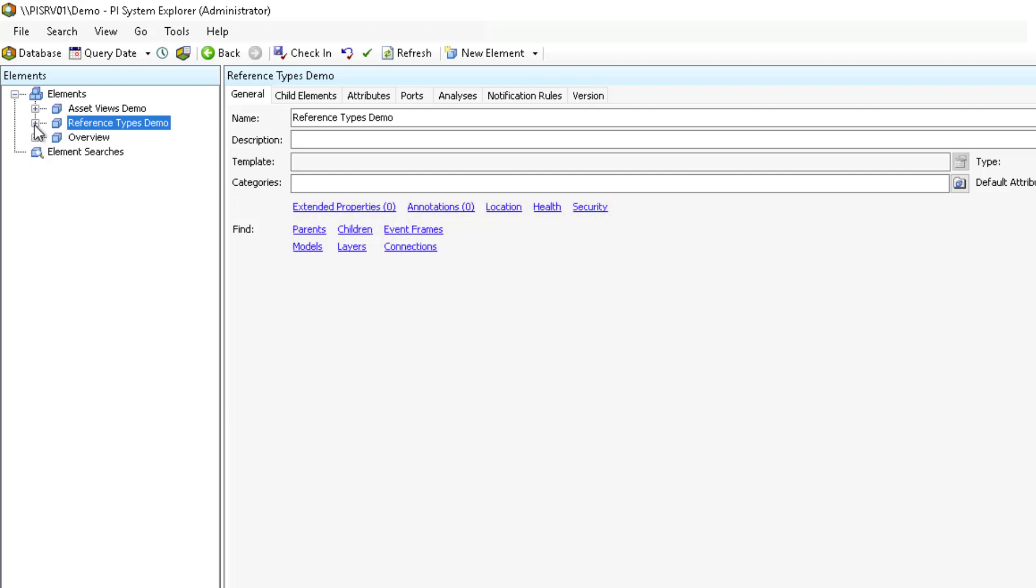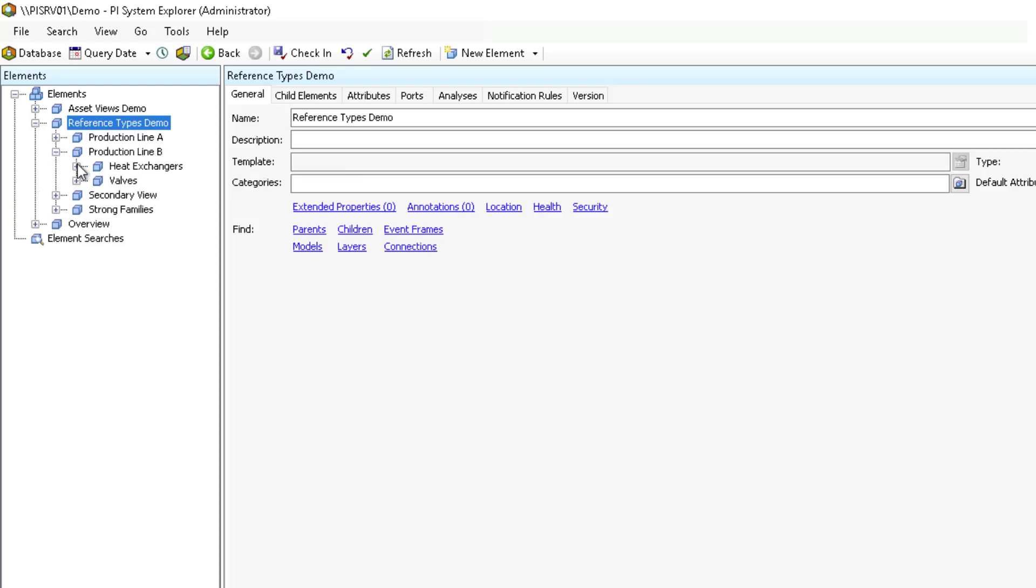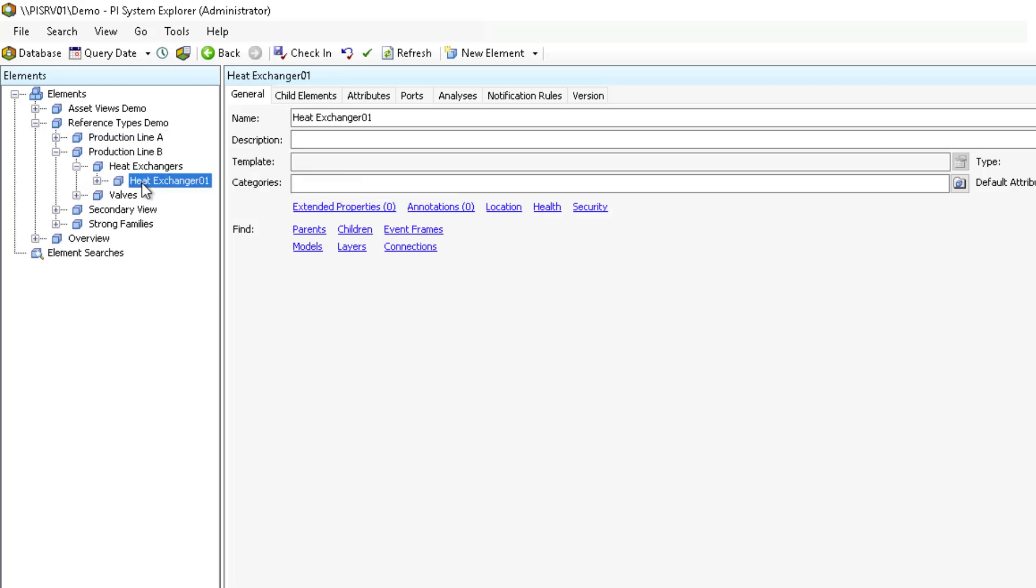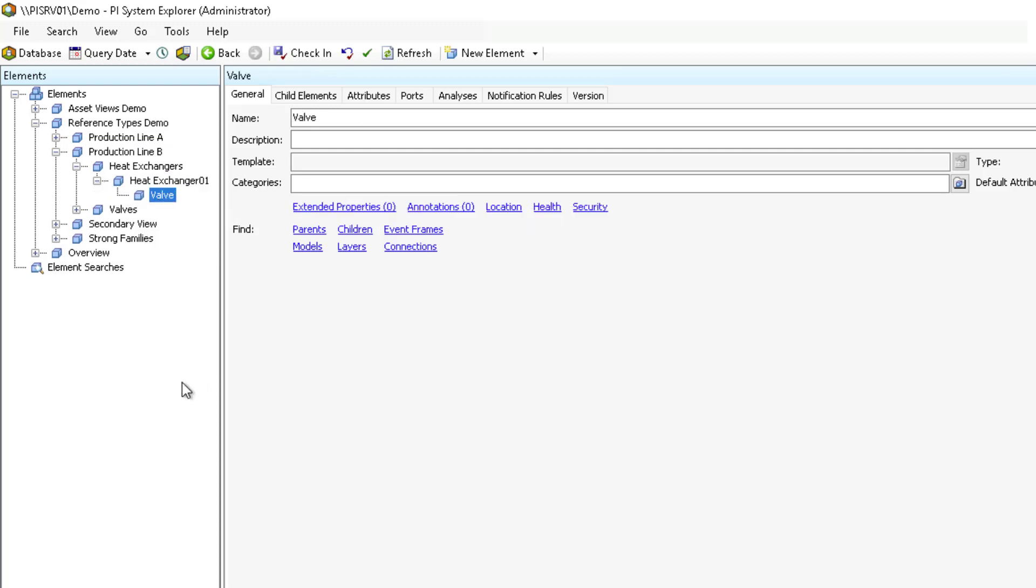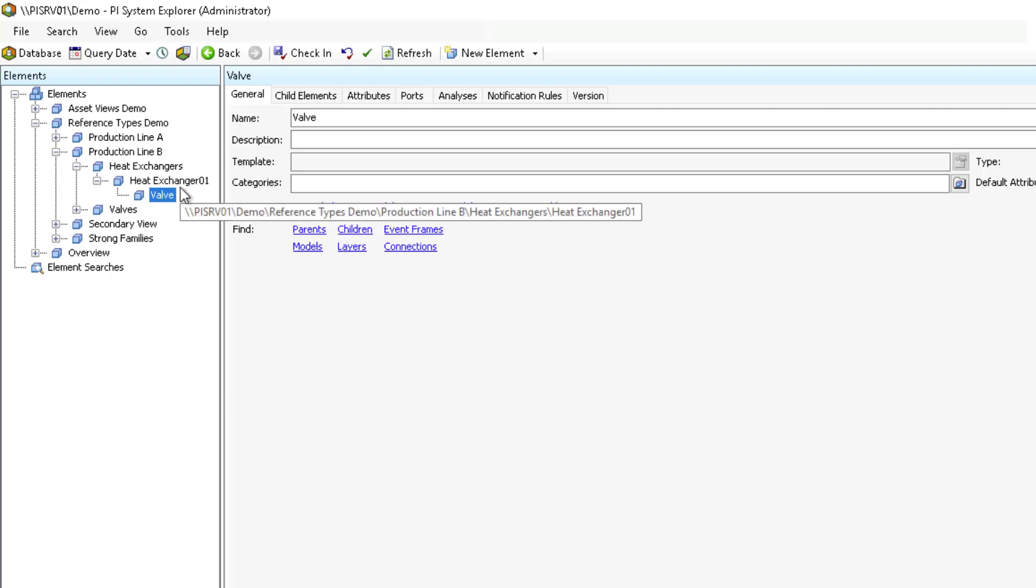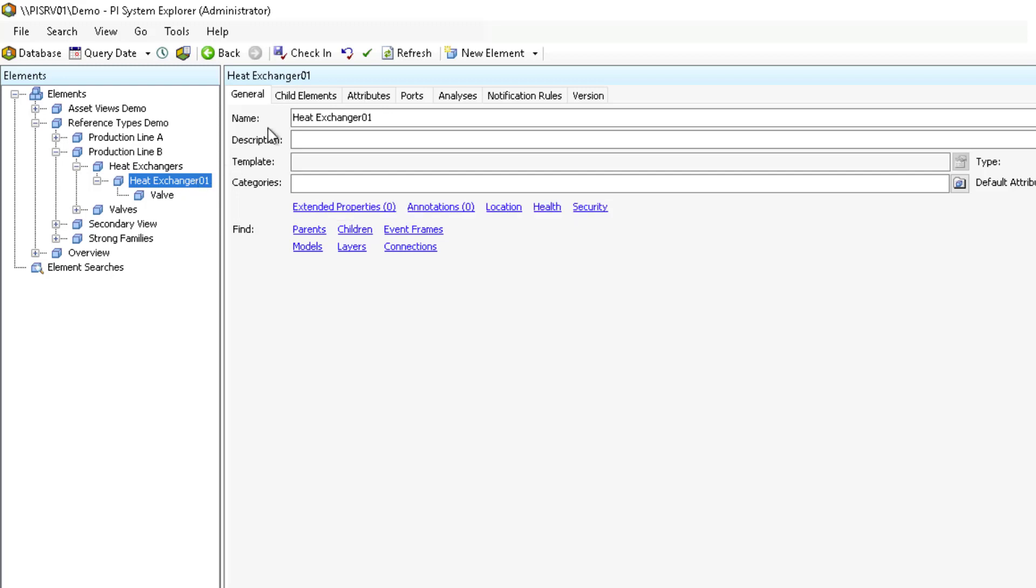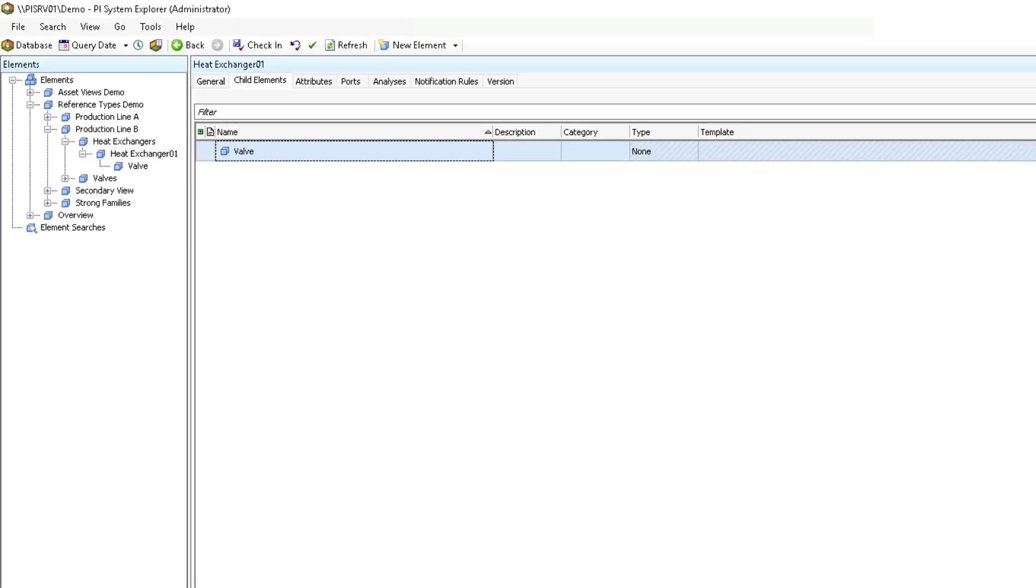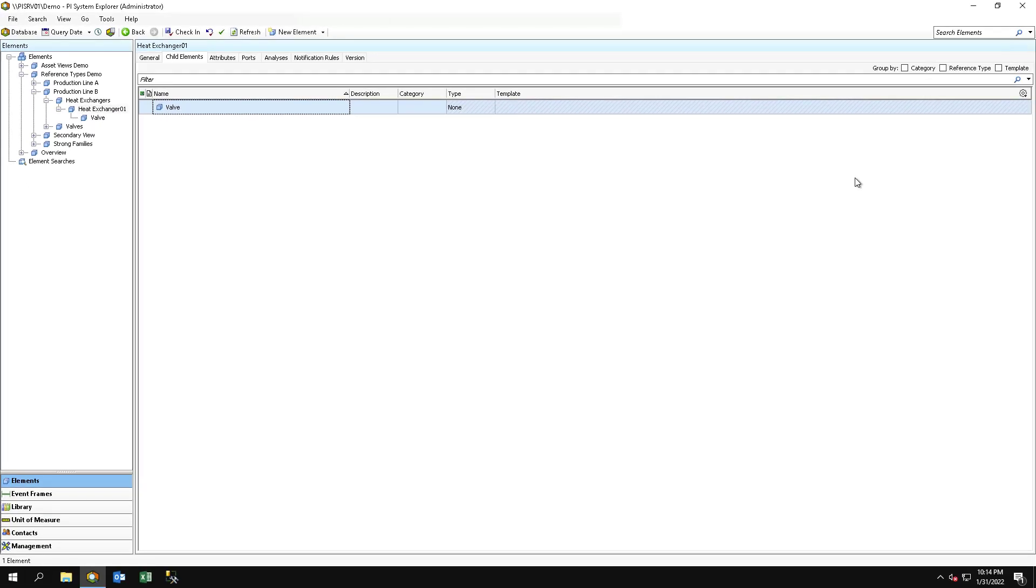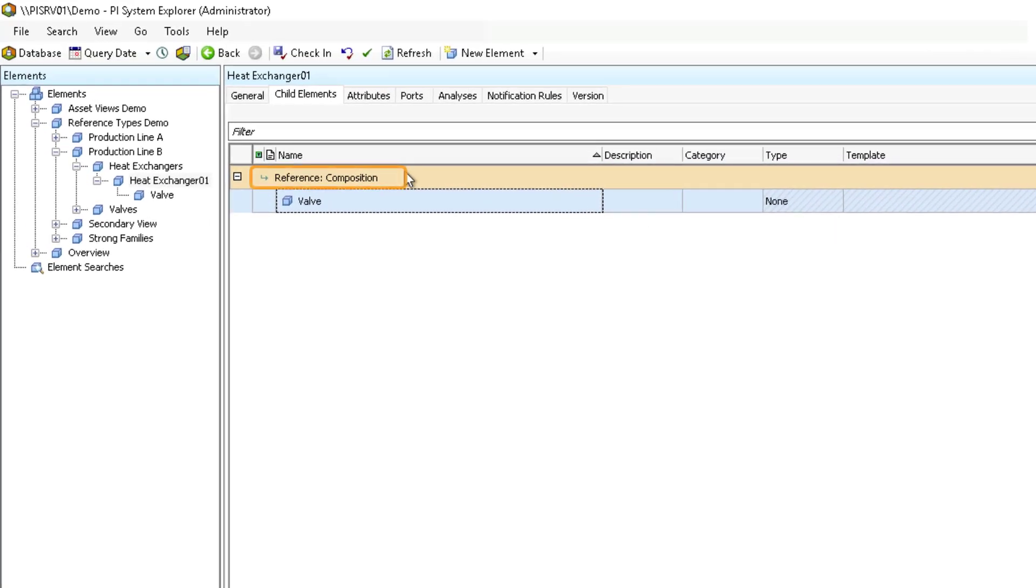In this first example, we have a heat exchanger called Heat Exchanger 01 in Production Line B. It has a valve that is an integral part of the heat exchanger and cannot exist on its own. Therefore, the relationship between the valve and the heat exchanger is composition. We can confirm this in PI System Explorer by clicking on the heat exchanger parent element and then selecting the child elements tab. Once on this tab, on the upper right, select group by reference type. And we will see that the child element valve has a composition element reference type.